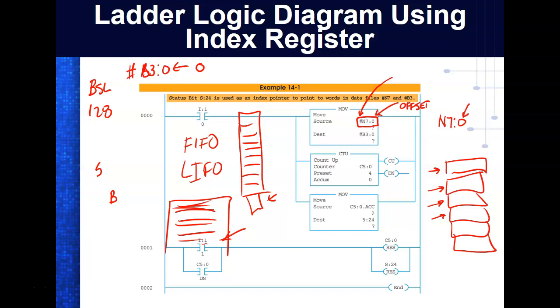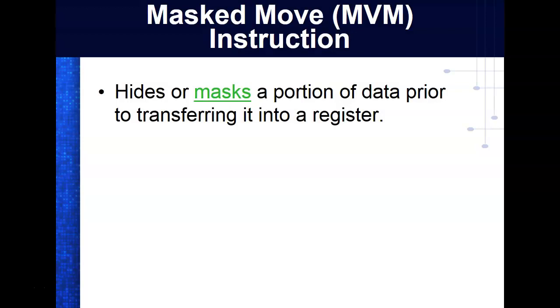It's using what we call a stack. So we establish what we call a top of the stack, and then the processor can manage going through the stack, putting stuff on it and pulling stuff off, right? Of course, we kind of cut out of sequence, but we don't have to, on the 1100s, set up a stack pointer. If you were on the 500s or the 1000s, then you would have to, if you wanted to change the stack pointer, then you could put something else in it. So by default, the 1100s start off with what? 0. And then we offset from 0.